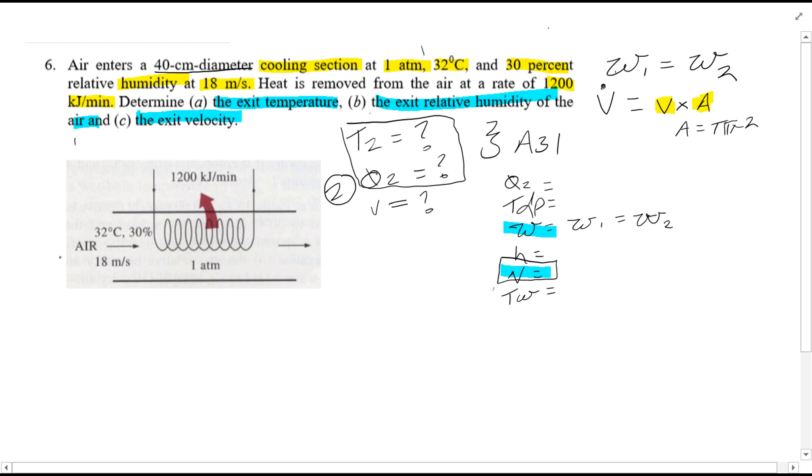Let's return to what we're given. We know at point 1, the temperature is 32 degrees C and relative humidity equals 30%. So using chart A31, as you've seen in previous videos, what we find here is W1 is equal to 9 grams of H2O per kilogram of dry air. Remember, W1 is also our W2.